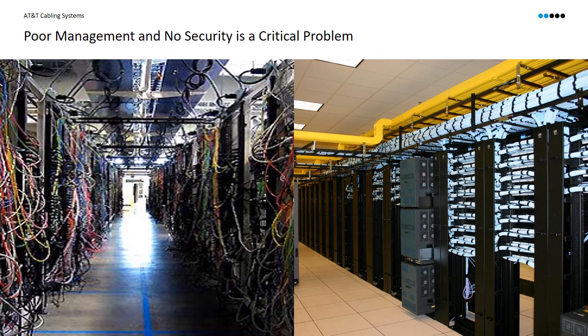Poor management and no security is a critical problem. If you have an installation with very poor administration, in a very short period of time you can go to a very serious patching mess. You can have a situation where if you wanted to do a move, add or change, it would be very difficult to organize. You'd have to remove all the patch cords and repatch again. It's a lot of downtime. If you wanted to fix a problem quickly, it would take a long time. And if you wanted to do an upgrade, you'd probably have to build a new data center and then refurbish the old one, which is just not practical.